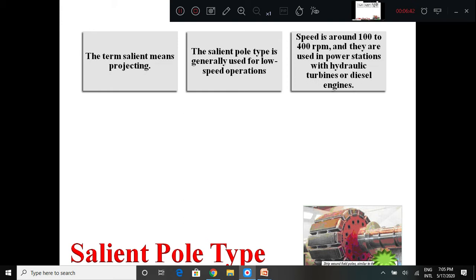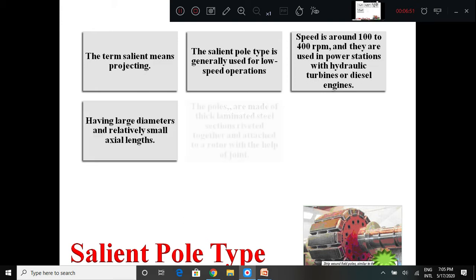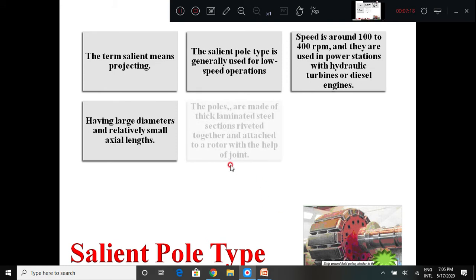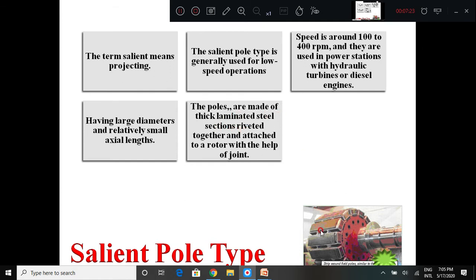The salient pole type of alternator rotor is used for low speed machines. It has a large diameter and relatively small axial length - the diameter of the rotor is more because the poles are projecting, but the axial length is small. The poles are made up of laminated steel, and are also made up of laminations stamped together to minimize hysteresis and eddy current loss. These poles are attached to the rotating body with the help of a joint.